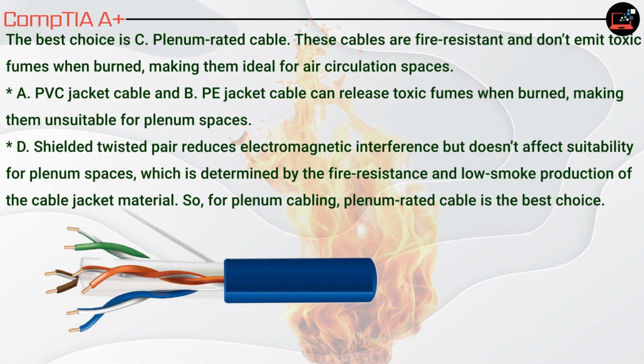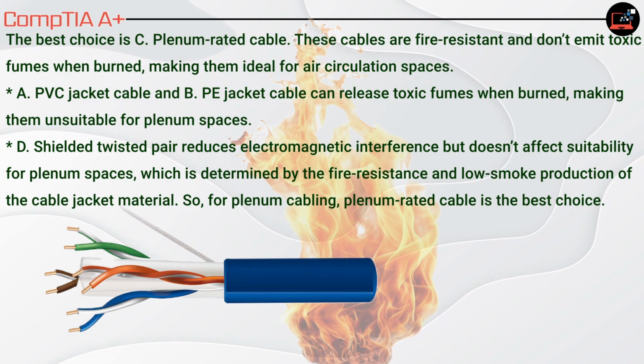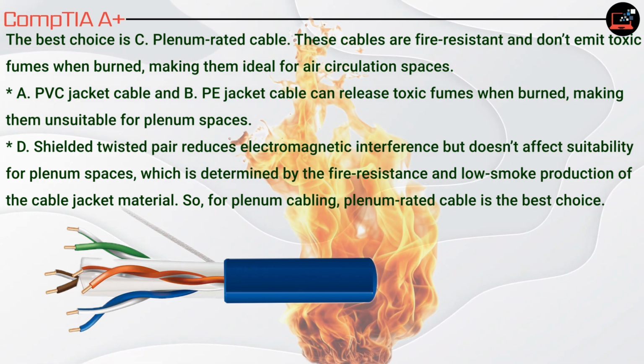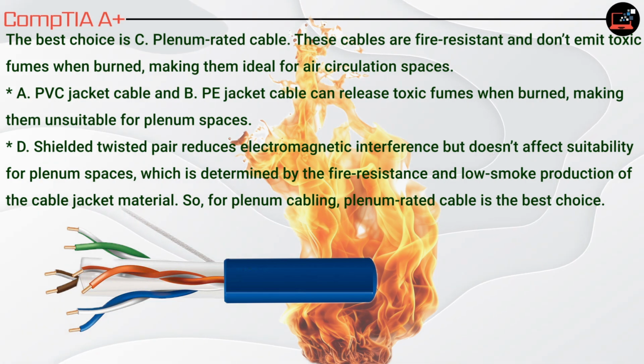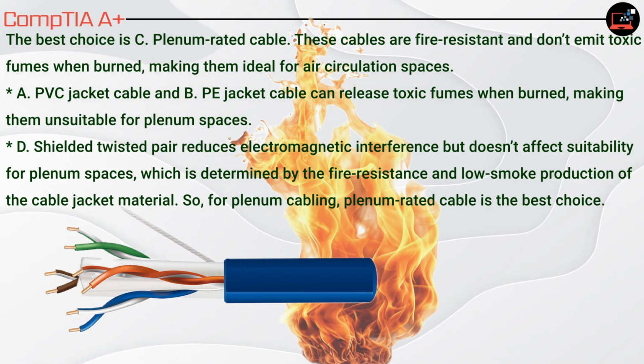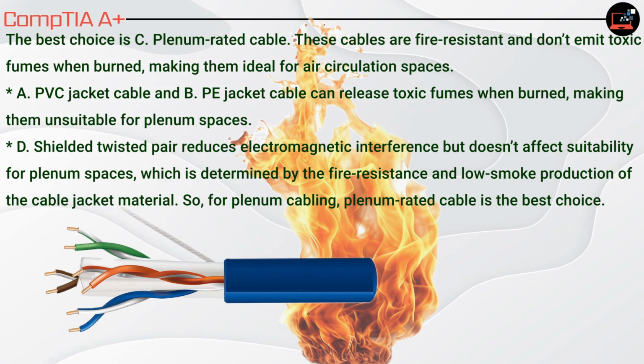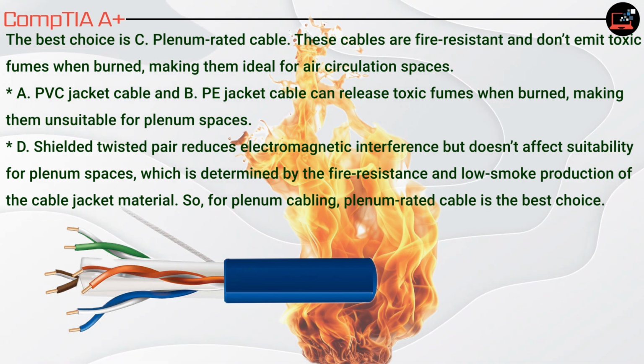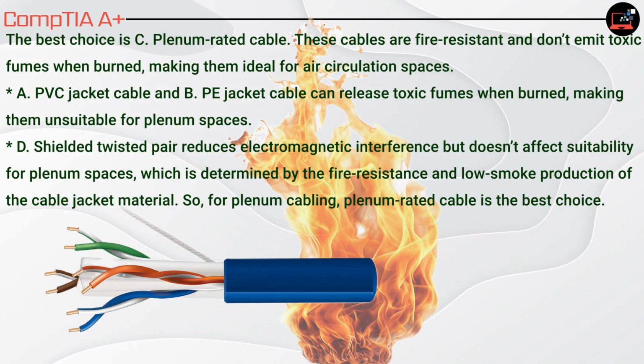These cables are fire resistant and don't emit toxic fumes when burned, making them ideal for air circulation spaces. A, PVC jacket cable and B, PE jacket cable can release toxic fumes when burned, making them unsuitable for plenum spaces. D, shielded twisted pair reduces electromagnetic interference but doesn't affect suitability for plenum spaces, which is determined by the fire resistance and low smoke production of the cable jacket material. So, for plenum cabling, plenum rated cable is the best choice.